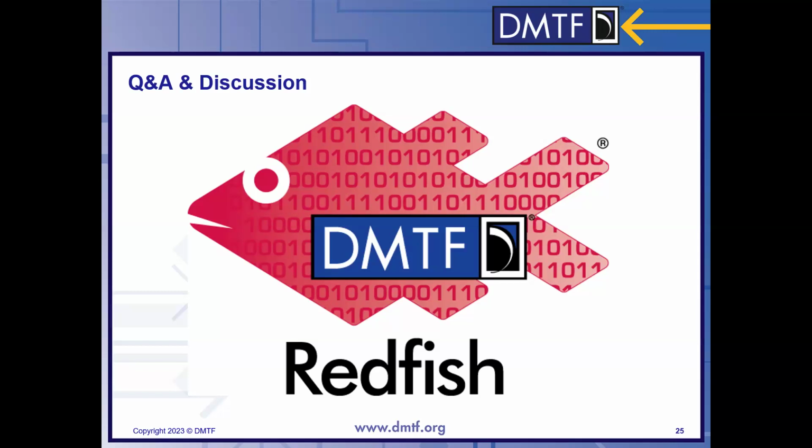So the way that Redfish works, it is a REST interface. It is based on HTTP. What we did was try to flatten the model as much as possible. So we divide those resources up, as I showed, where you get a lot of information with one GET, and then you shouldn't have to be doing those over and over again. So you get one resource and get many pieces of data, and then we keep those resources small when there's a lot of changing information, metrics, and so forth.